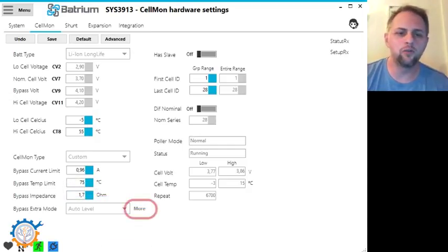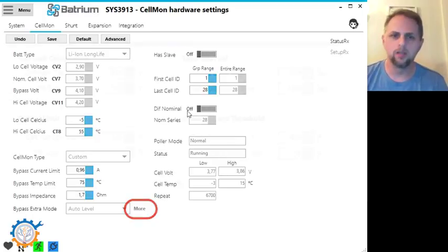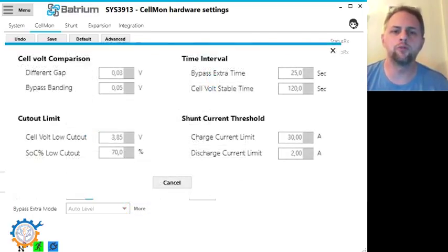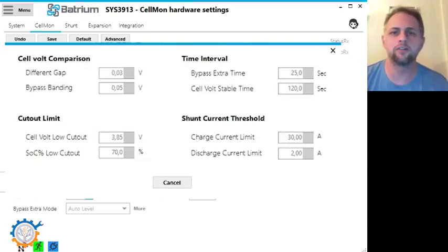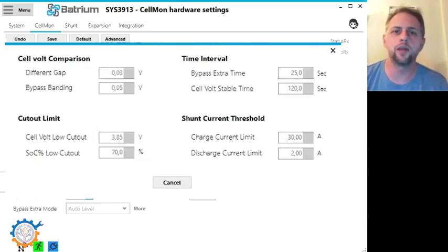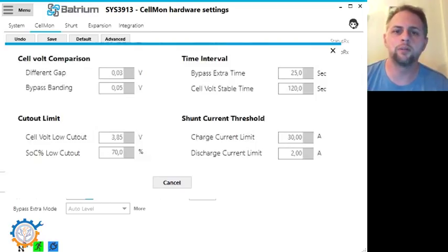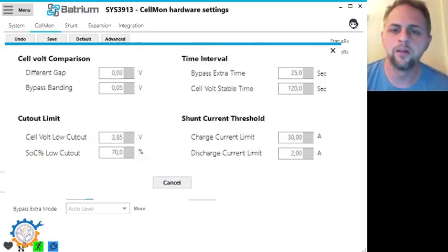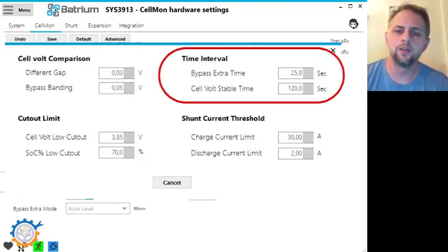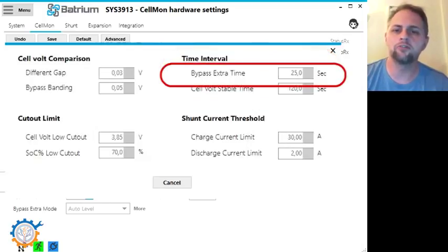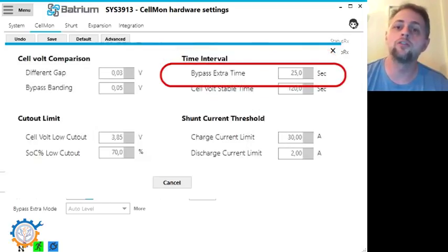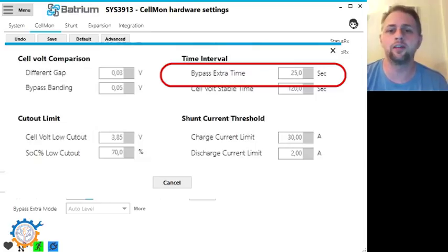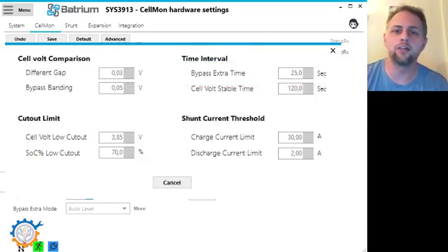To set the values for the auto level functionality you go into the more. In the more window you have four categories where you can set different type of values to be able to do the auto level functionality. You have something that is called a time interval. The bypass extra time is the amount of seconds it bypasses or tries to level the cell each time before it actually recalculates the values it has.